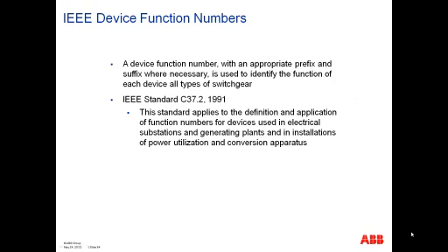For the IEEE device function numbers, you want to refer to the standard C37.2, last revised in 91, but revised again just recently. A device function number with an appropriate prefix and suffix where necessary is used to identify the function of each device in all types of switchgear.